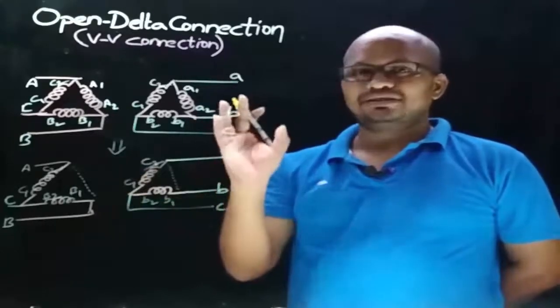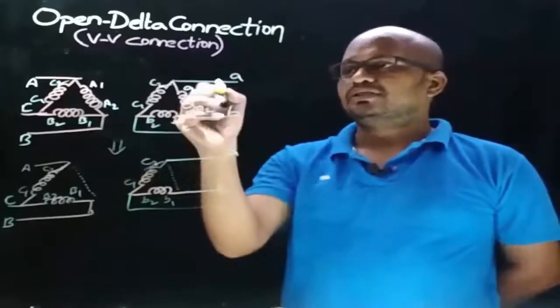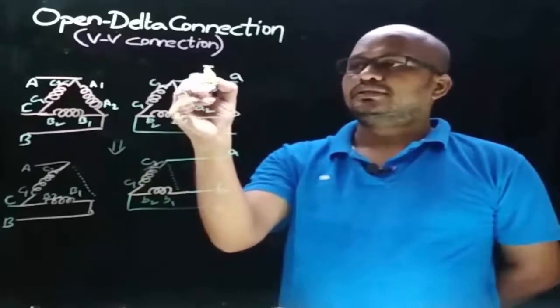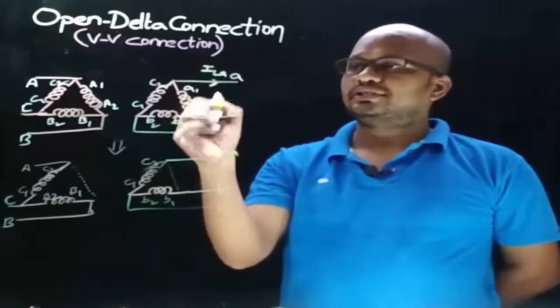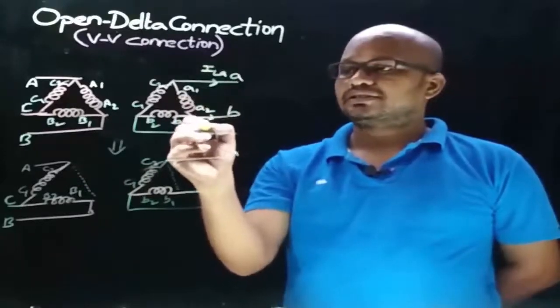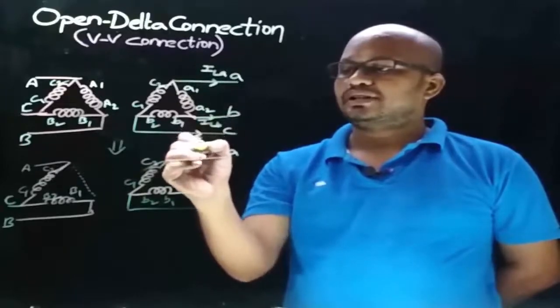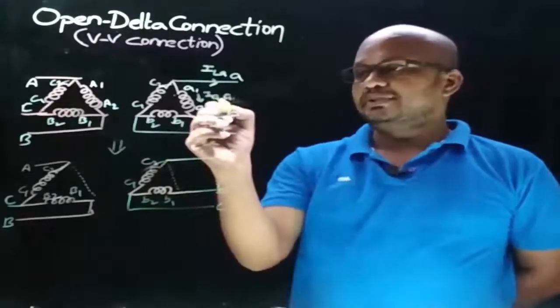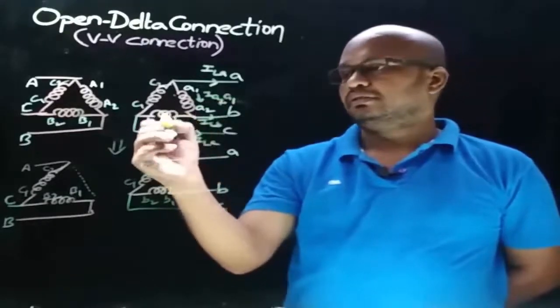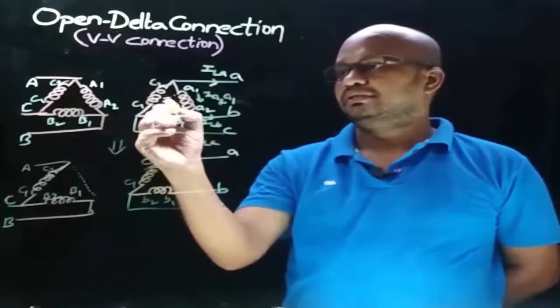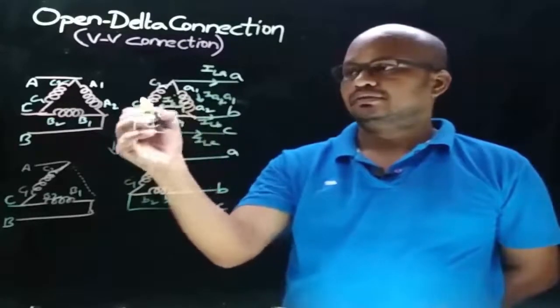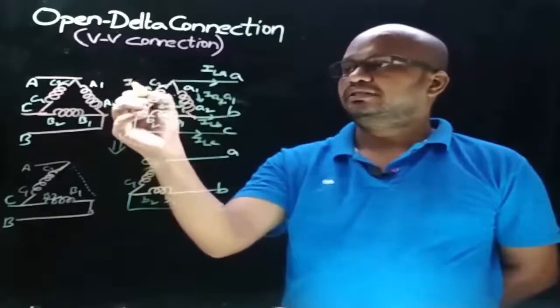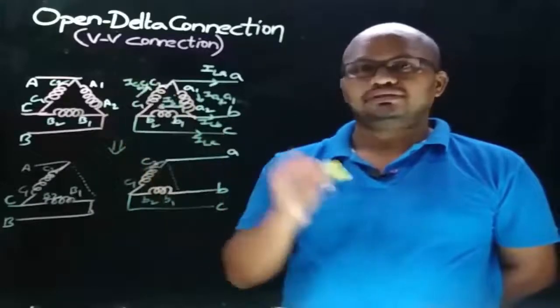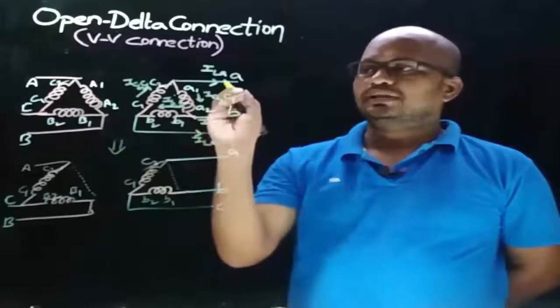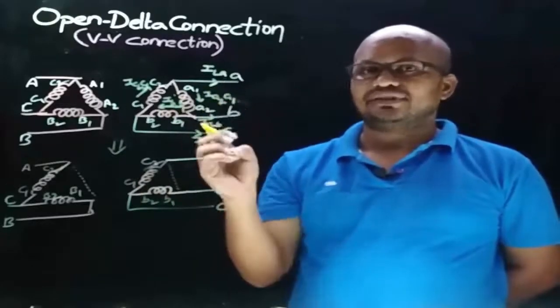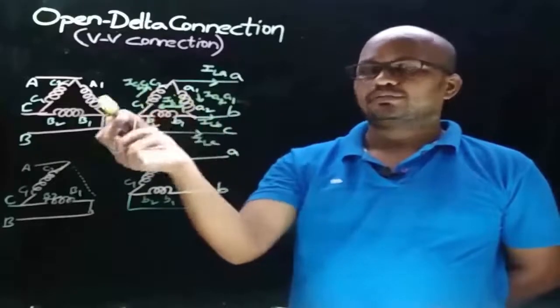For that, let's mark the currents in the secondary windings. So this is the secondary side line current ILA, this is ILB, and this is ILC. And the phase currents be IA to A1, IB to B1, and IC to C1. So when one of the transformers in delta-delta connection gets failed, what we assume is that transformer 1 got failed.